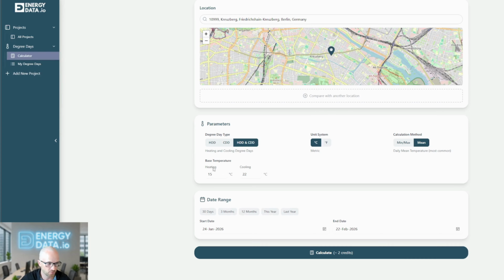In Europe, or in Germany, it's 15, in the UK I think it's 15.5 degrees Celsius. How to define the individual base temperature for your building, I will show in a different video. We just go with the basic values of 15 degrees for heating and above 22 for cooling.